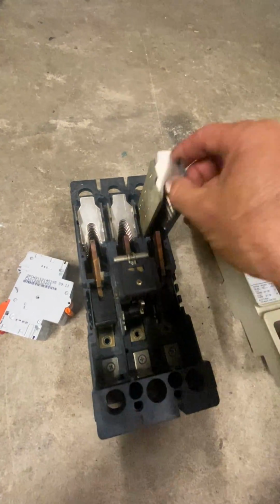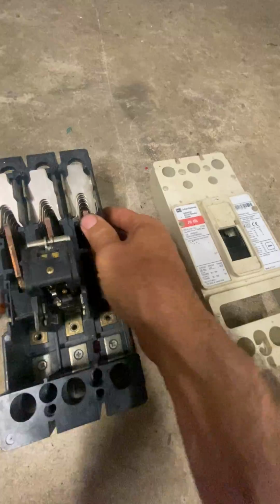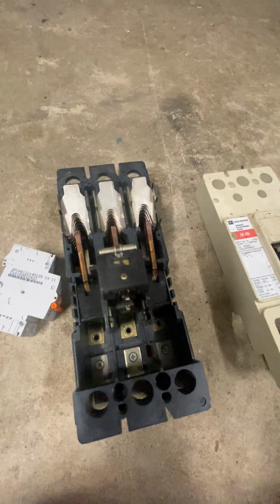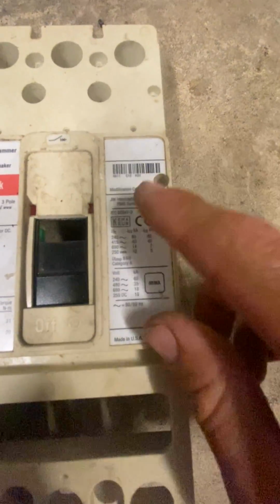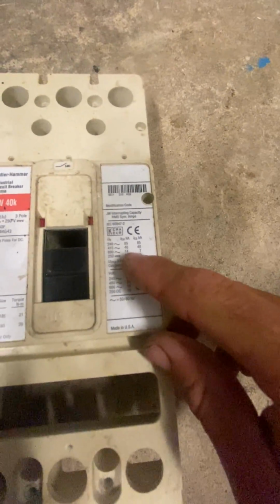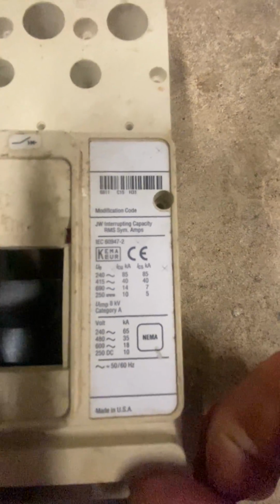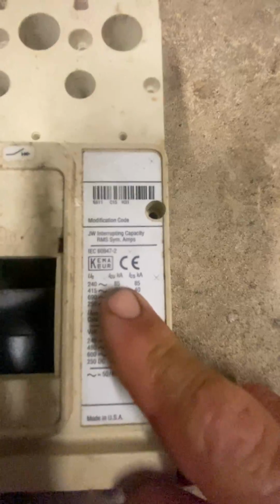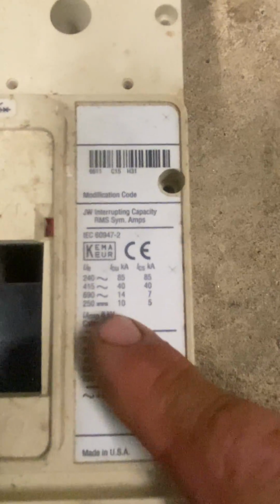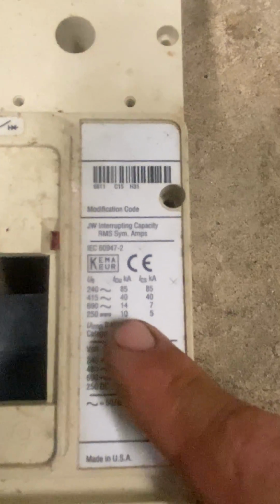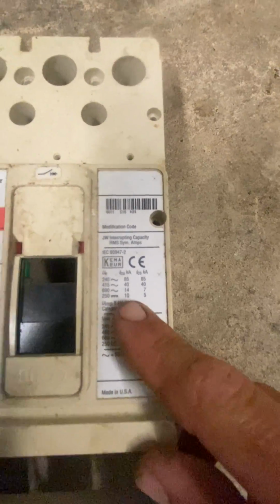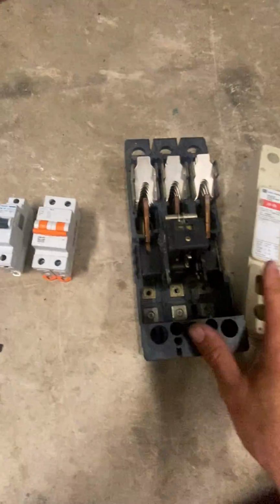So that's very, very important, because these chutes and this gap dictate its fault current rating, which is different for AC and DC applications. An example of that is here. You can see there on this one, under 240 volt, the fault current rating is 85,000, but under DC applications it's only 10,000. So it's very, very different between the two. That's because the way AC and DC operate is very, very different.